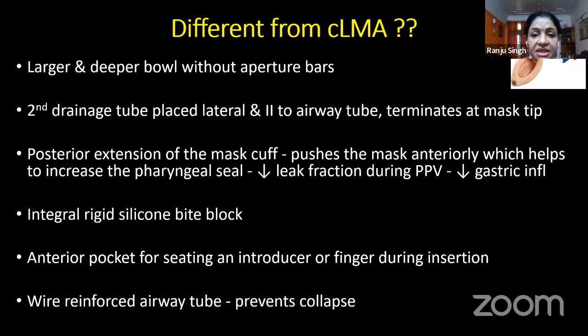There is a posterior cuff, and this posterior cuff pushes the mask and creates a better pharyngeal seal. Along with this posterior cuff and the large bulk of the ProSeal, a very good pharyngeal seal is created, which means that there is less leak during positive pressure ventilation and less risk of gastric inflation, which means there is less risk of regurgitation and aspiration of those regurgitated contents. There's an integral bite block, which is missing in the CLMA. There is an anterior pocket for an introducer or using your finger during insertion. And there is a wire reinforced tube, which is missing in the classic LMA.